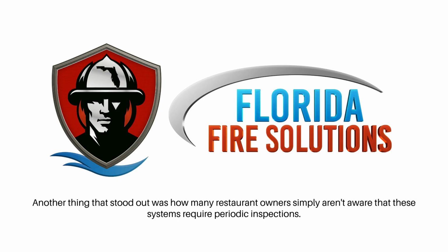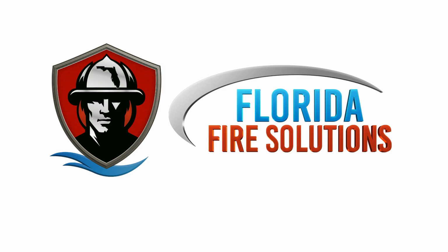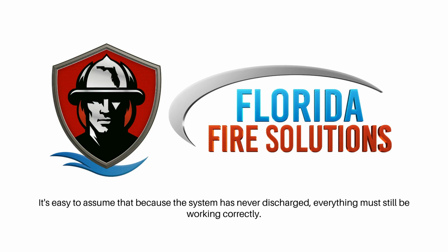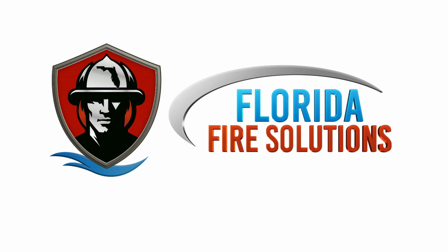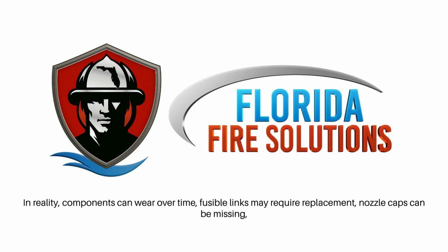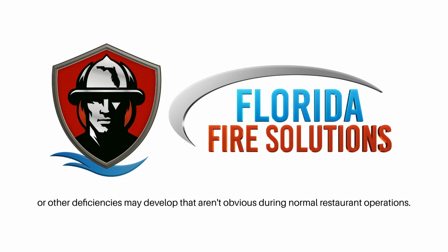Another thing that stood out was how many restaurant owners simply aren't aware that these systems require periodic inspections. It's easy to assume that because the system has never discharged, everything must still be working correctly. In reality, components can wear over time. Fusible links may require replacement, nozzle caps can be missing, or other deficiencies may develop that aren't obvious during normal restaurant operations.